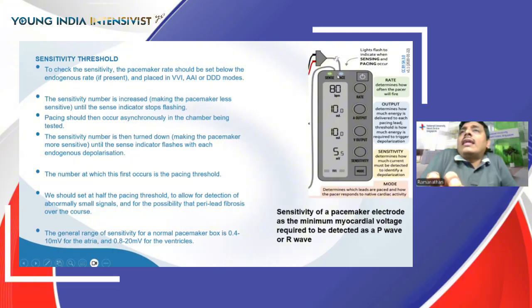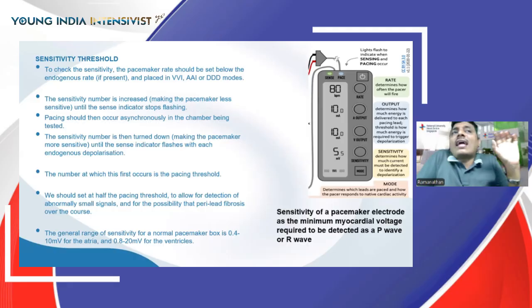There are two indicators on the top of the pacemaker. One is sense and the other is pace. You increase this number till the sense indicator stops flashing. Pacing should then occur asynchronously. Once you reach that point, you then turn down the sensitivity number, so the pacemaker becomes more sensitive, till the sense indicator starts flashing again, which means it starts detecting the endogenous depolarization. The number at which this first occurs is called the pacing threshold. And usually when you set it on your pacemaker, you set it at half the pacing threshold.